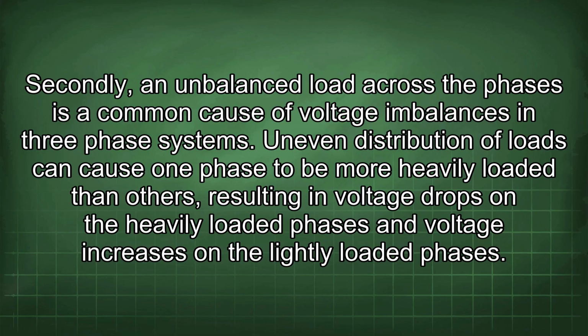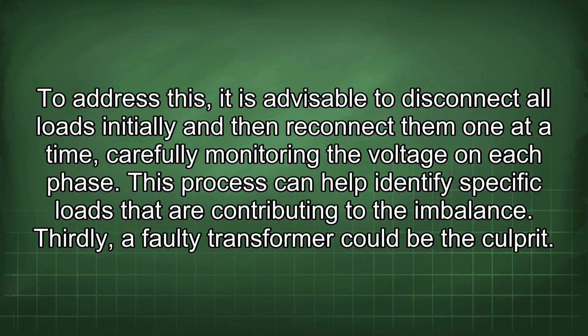Secondly, an unbalanced load across the phases is a common cause of voltage imbalances in three-phase systems. An uneven distribution of loads can cause one phase to be more heavily loaded than others, resulting in voltage drops on the heavily loaded phases and voltage increases on the lightly loaded phases. To address this, it is advisable to disconnect all loads initially and then reconnect them one at a time, carefully monitoring the voltage on each phase. This process can help identify specific loads that are contributing to the imbalance.